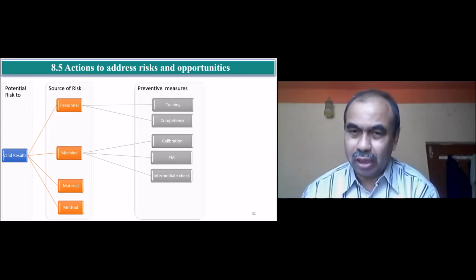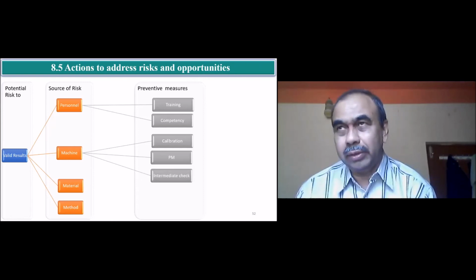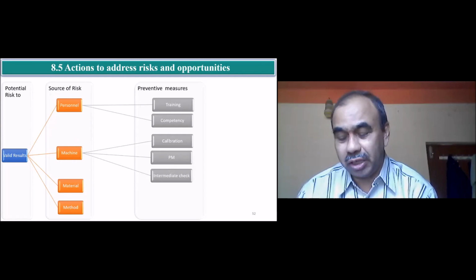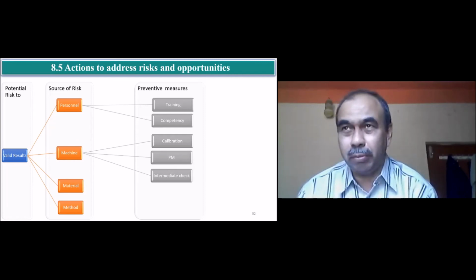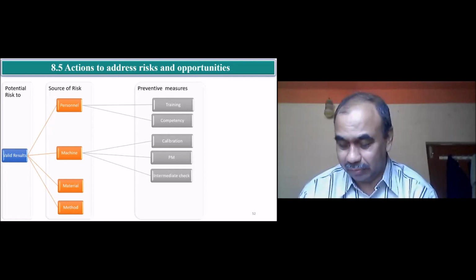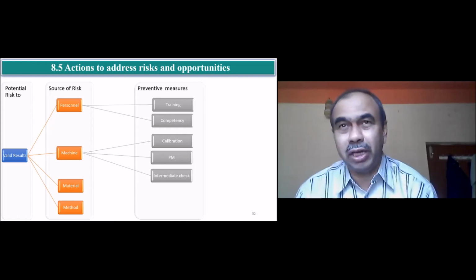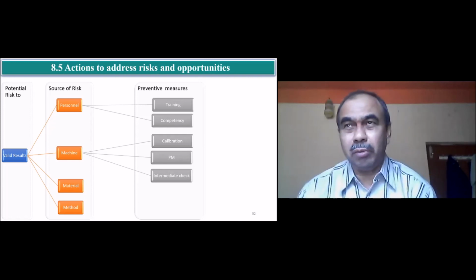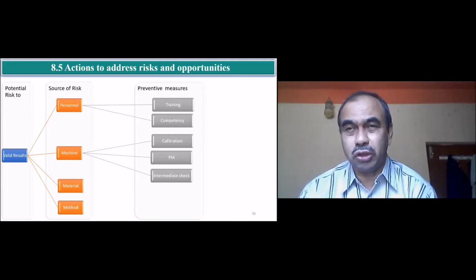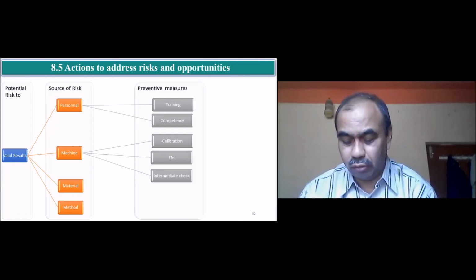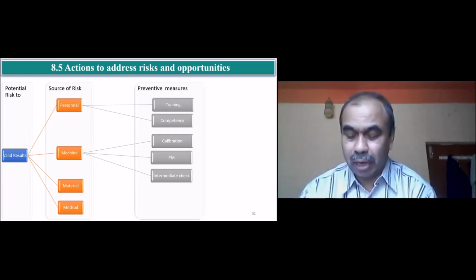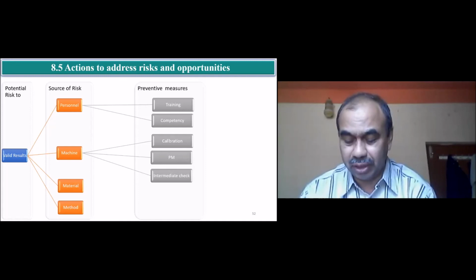Secondly, your calibration plan and calendar. Looking into the validity of the results, you have to check whether your plan and calendar are suitable to the number of tests you are performing periodically, one monthly or half yearly or something like that. Then you have a risk. What is this risk? If you are too frequent, you may fail because you don't have any alternative instrument. The time consumed by the external suppliers is too high. So accordingly, you have to plan. Here is a risk, and that is the action. Planning your calibration plan and calendar is very important here.